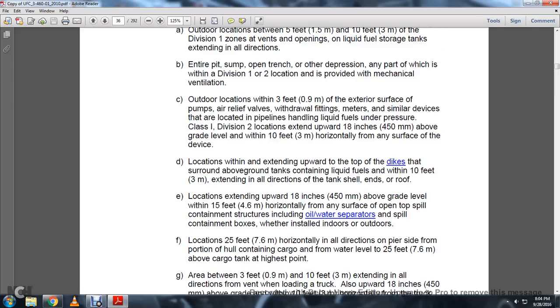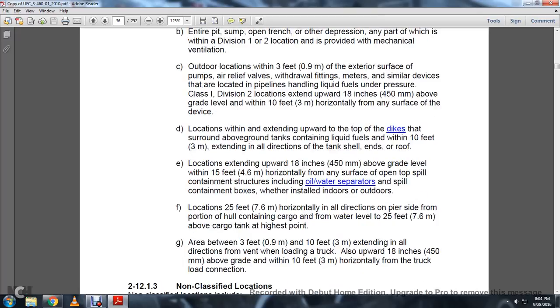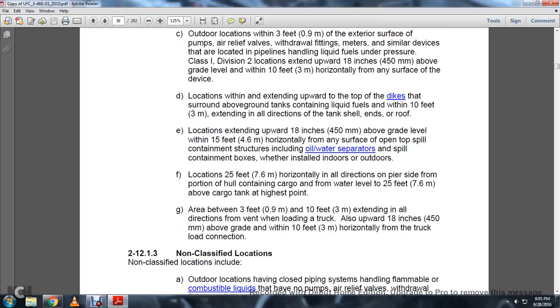Locations extending upward to the top of the dikes surrounding aboveground tanks containing liquid fuels, within 10 feet or 3 meters extending in all directions of the tank shell, end, or roof. Locations extending upward to 18 inches above ground level within 15 feet horizontally of any surface of the open top spill and containment structures, including oil water separators and spill containment boxes, whether installed indoors or outdoors.